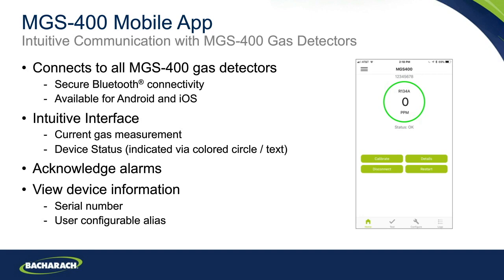that intuitive interface. We can see here on the main screen that you'll see in the app, we're going to get the gas type, we're going to get the current gas measurement and the status on there of whether we're okay or whether we have any alarm thresholds being surpassed, which will be indicated with color coding as well as text. And there are also ways in here to acknowledge alarms if they're in place and to go in and view the full device information as well, so pulling out things such as the serial numbers. And there is a user configurable alias within the system here as well, so you can name each detector to tie it into the specific location or asset that it is there to monitor.